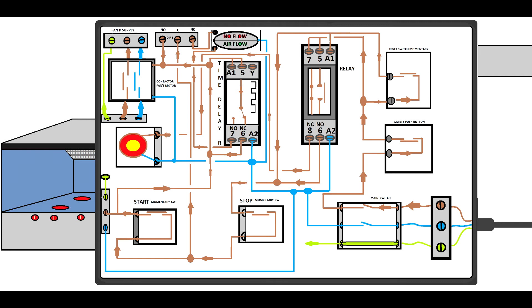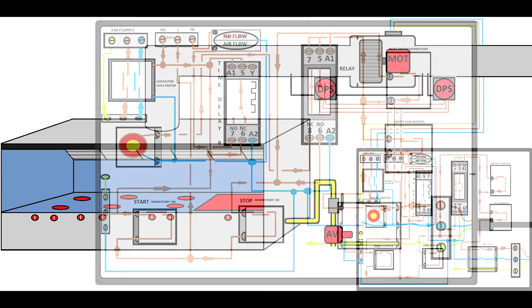You have to know a little bit about the differential pressure switches and where they're used. They're used in the ducts before and after the fan. You can use one, two, or three - it doesn't matter how safe you want to make your system. You have to know what a time delay relay is and how the time delay relay will override the differential pressure switch, then turn off, and then the differential pressure switch will override the time delay relay to keep the gas valve open.